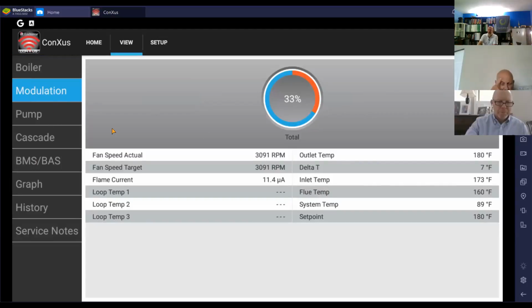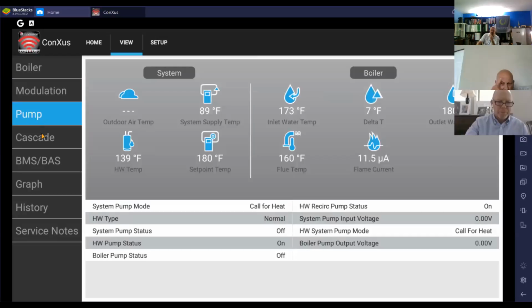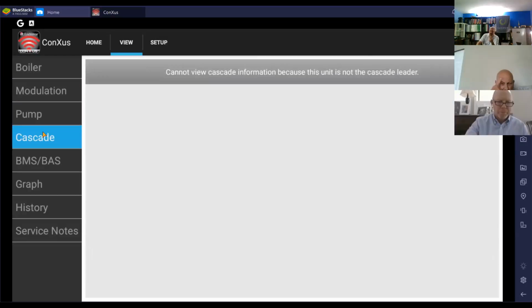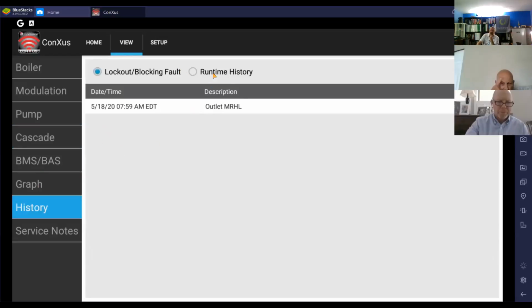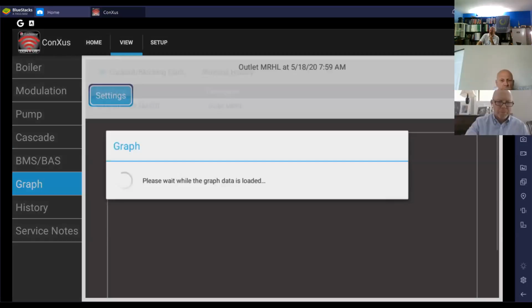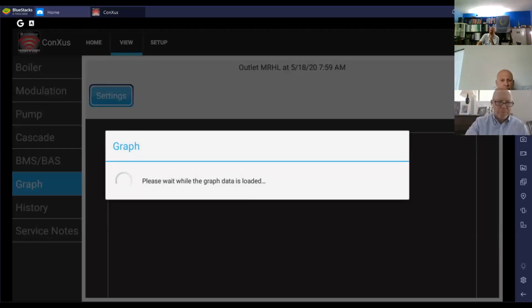Don't worry, Bill, we'll go see what the boiler that's locked out is locked out on - I'm hoping it's one of yours, and we'll take a look at it. What's my pump doing? In this case, this is not the cascade leader, so I can't see that information here. Let's get into some history - so here they had a manual reset high limit. I know they've been doing some work, but let's see what was going on at that moment in time, which is what we're going to do. So this is going to take us back to May 18th at basically 8 a.m.